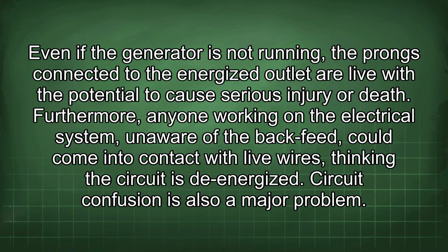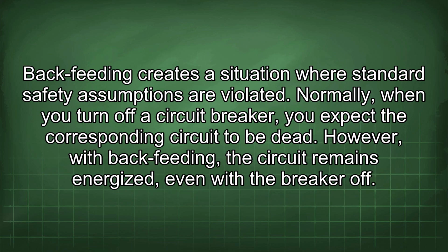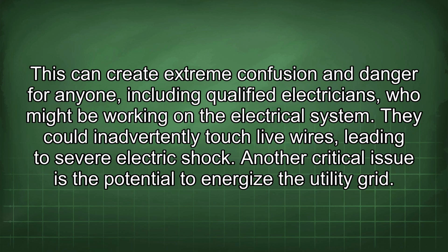Furthermore, anyone working on the electrical system, unaware of the backfeed, could come into contact with live wires, thinking the circuit is de-energized. Circuit confusion is also a major problem. Backfeeding creates a situation where standard safety assumptions are violated. Normally, when you turn off a circuit breaker, you expect the corresponding circuit to be dead. However, with backfeeding, the circuit remains energized even with the breaker off. This can create extreme confusion and danger for anyone, including qualified electricians, who might be working on the electrical system. They could inadvertently touch live wires, leading to severe electric shock.